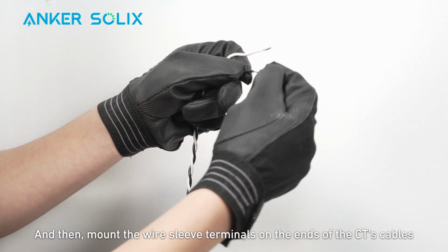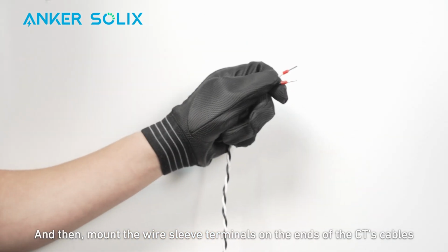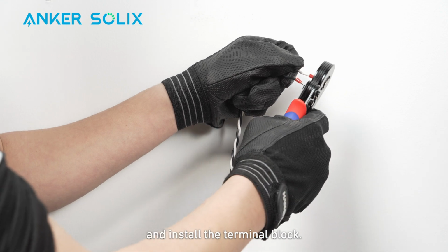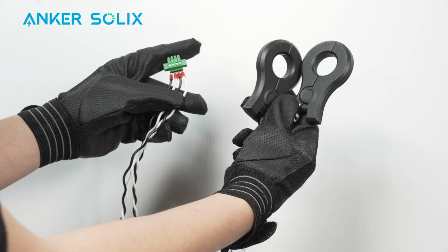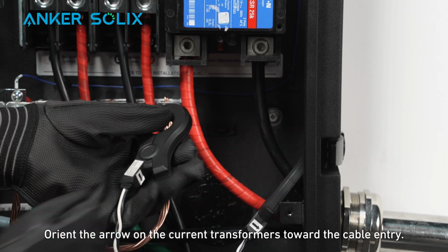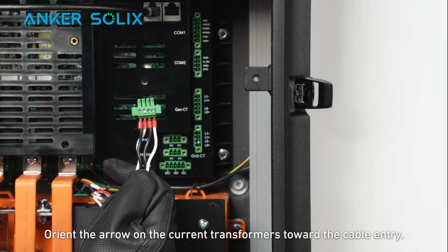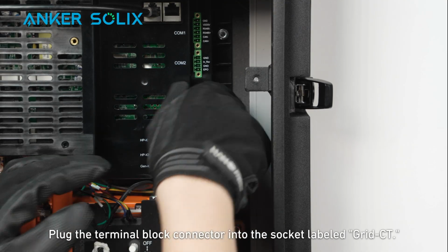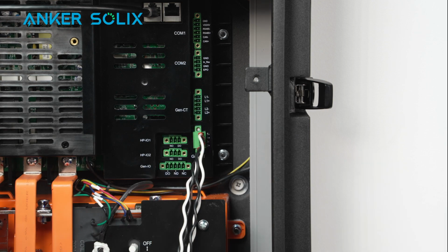And then, mount the wire sleeve terminals on the ends of the CT's cables and install the terminal block. Orient the arrow on the current transformers toward the cable entry. Plug the terminal block connector into the socket labeled Grid CT.